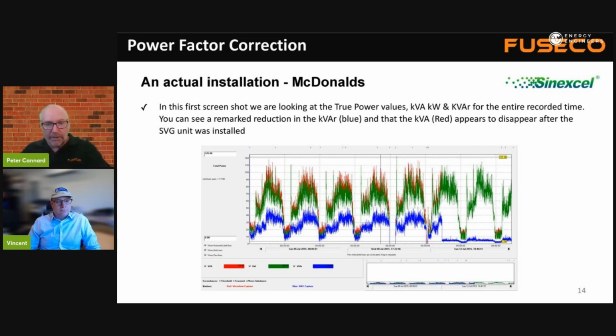This is an extended recording, with various processes changing over time per day. Once you get about three-quarters of the way over to the right-hand side, you'll see the blue go down almost to zero - that's because we've got a power factor correction cabinet installed now. It's listening, measuring and recording the current flow, working out the displacement between current and voltage, and then bringing the current flow back in line with the voltage.